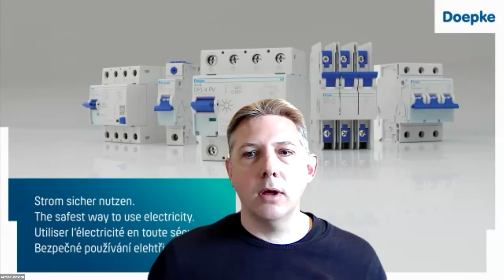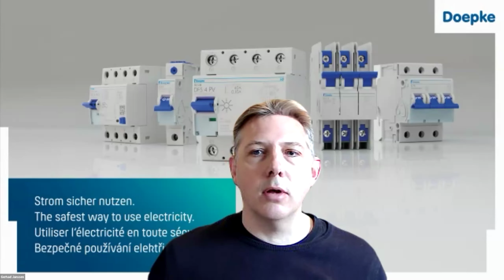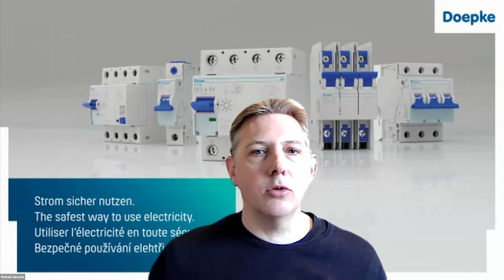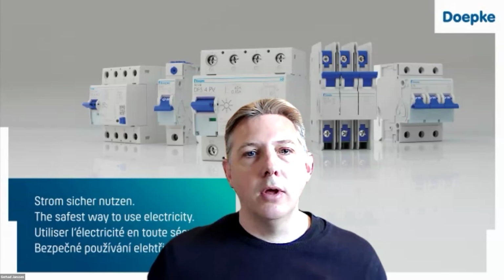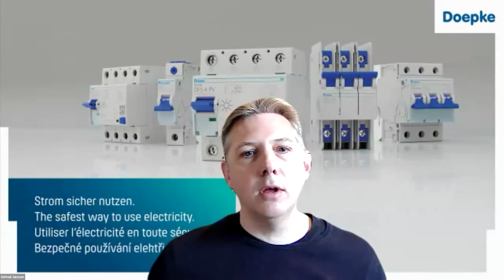Is the test button being used frequently or not? If you do not use the test button for 20 years, I think the RCCB will not work mechanically anymore. So it really depends on the application and on the breaker. So there is no certain lifetime in the norm yet. It is being discussed, but not yet, I would say.